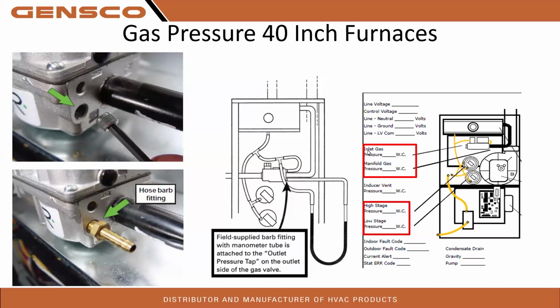And we're simply going to put the inlet gas pressure and the manifold gas pressure. So inlet is what's coming in from the house, right? It can't be over 14 because we can't open our gas valve. Natural gas, obviously, NG and LP are going to be different. And then of course, if we have a two-stage unit, low stage pressure we want to know, and of course the high stage pressure we want to know.